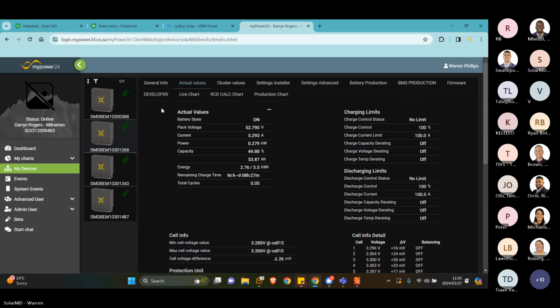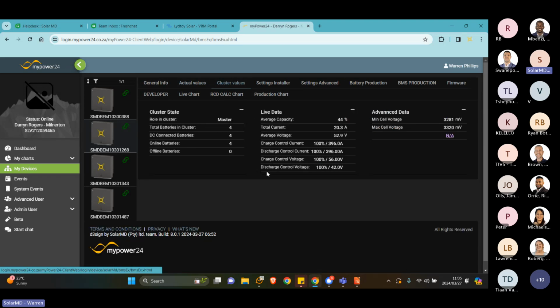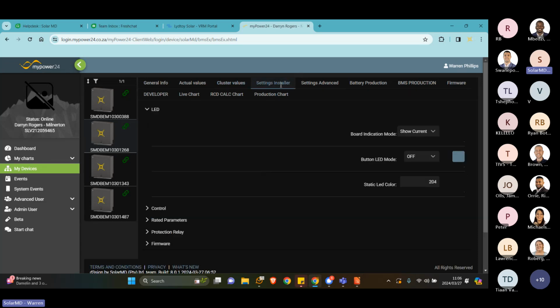So that's looking at the individual stats of the battery. Here you can see the cluster values, which are the combined values being sent by all 4 batteries to the inverter - the total charge and discharge current limits, the average voltage of the 4 batteries, and so on. This is what's reported to your inverter at the end of the day. So you can look at the individuals, but here you can see the data getting reported, and the minimum and maximum cell voltages for the cluster itself.